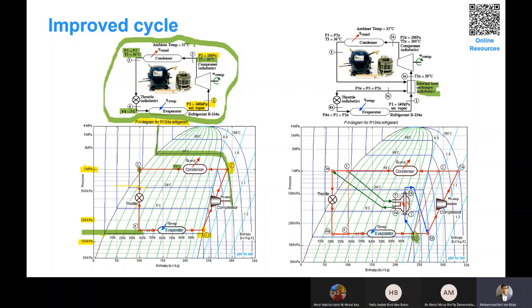So you bring the temperature from minus 22 up to the right, to plus 20. So this is the condition now at 1x. And then we compress, instead of having at 0.2 before, now you have at 0.2x, and the temperature increased from 60 before to 100 degrees Celsius.